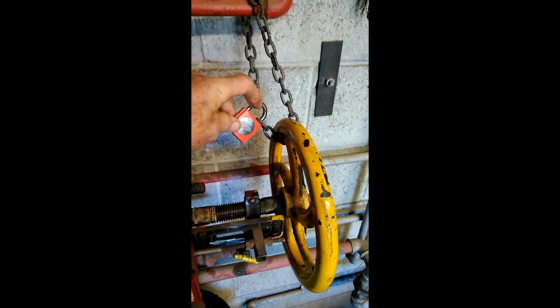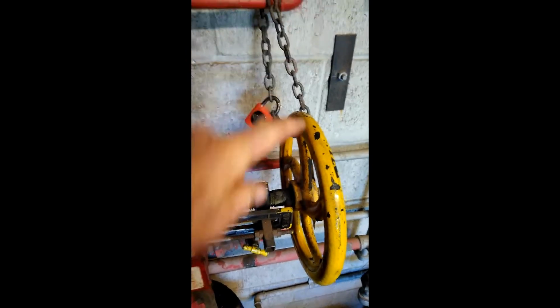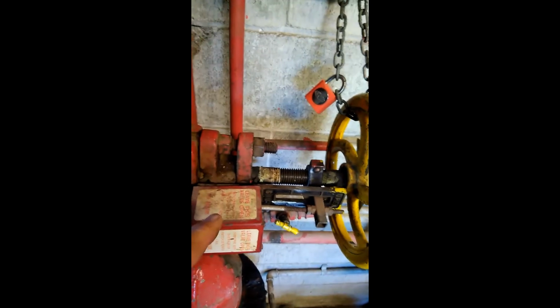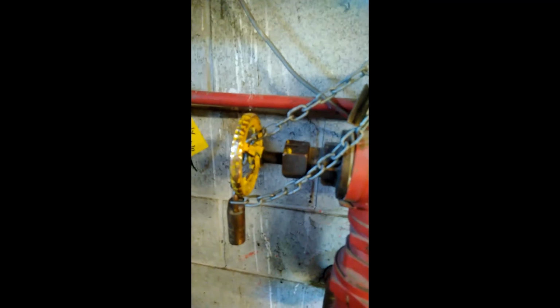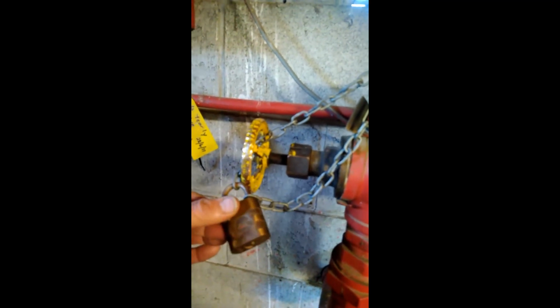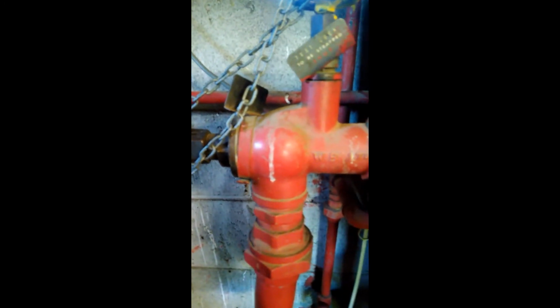You come back, your water gong, isolate that. Then you come back to your main stop valve, unpadlock that and shut the main stop valve, and then you can come over to the drain valve, unlock that and drain the system.